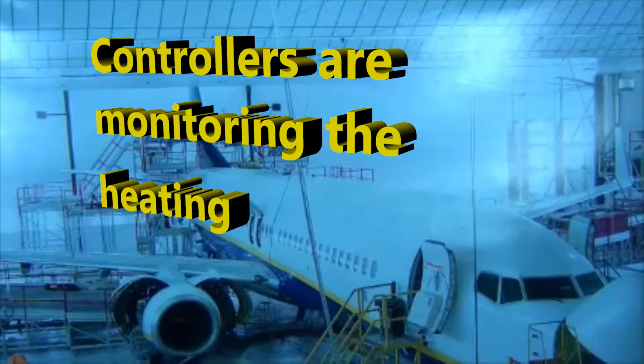Okay, so looking at the monitoring that goes on with these controllers, they are monitoring the heating for all of what I mentioned just a bit ago. Low heating, or an overcurrent, or heating loss, or a discrepancy between the ground and the flight information. If there's a discrepancy there, then there's going to be an indication right away, a warning about that. Of course, you have internal circuits, that's a given, you have your internals and your externals. So that gives you an idea of the probe heat controllers and the channels that are involved with the anti-ice protection for the probes.